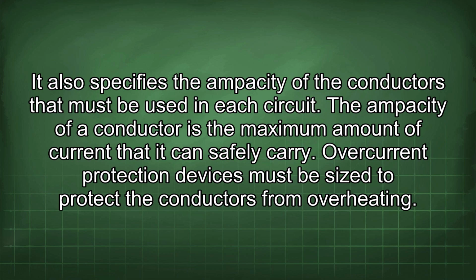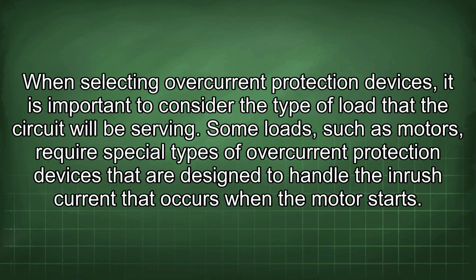The ampacity of a conductor is the maximum amount of current that it can safely carry. Overcurrent protection devices must be sized to protect the conductors from overheating. When selecting overcurrent protection devices, it is important to consider the type of load that the circuit will be serving. Some loads, such as motors, require special types of overcurrent protection devices that are designed to handle the inrush current that occurs when the motor starts.